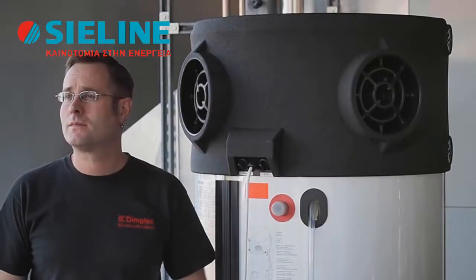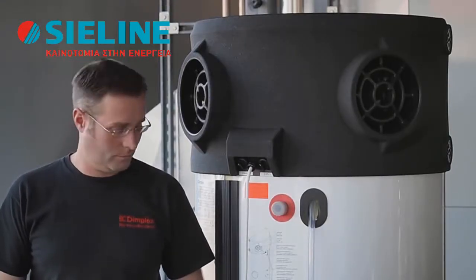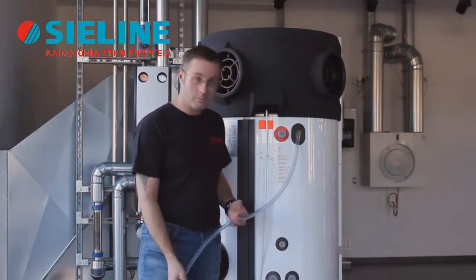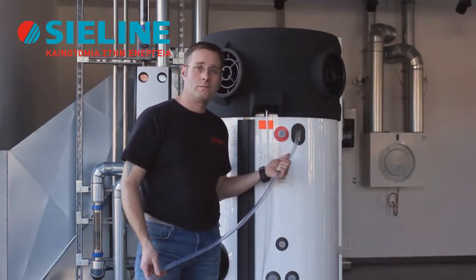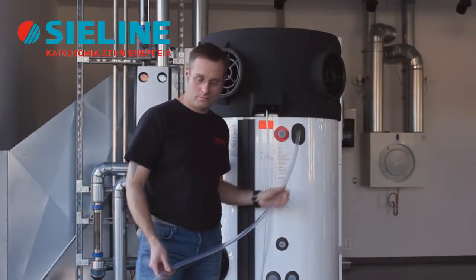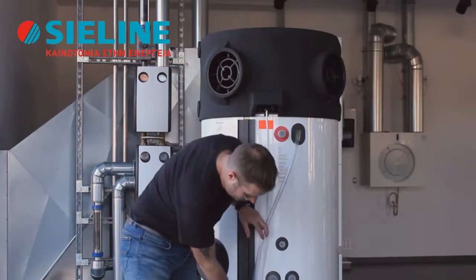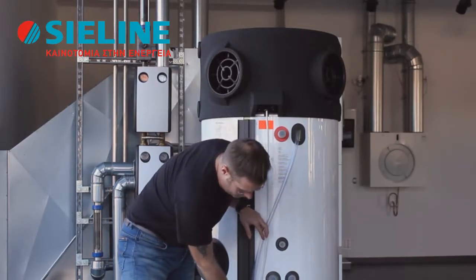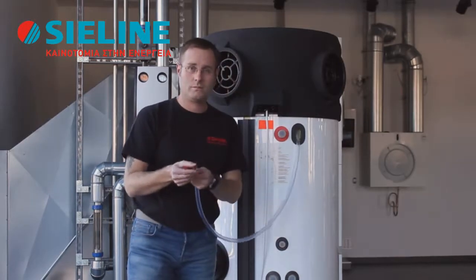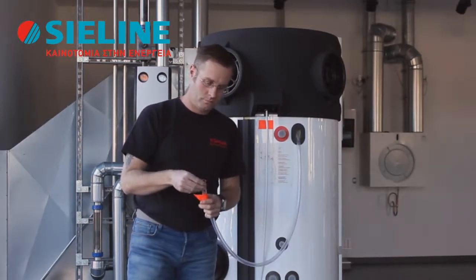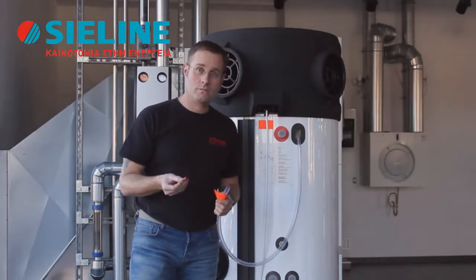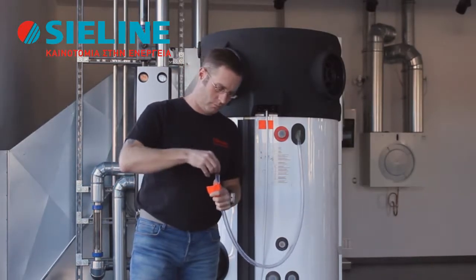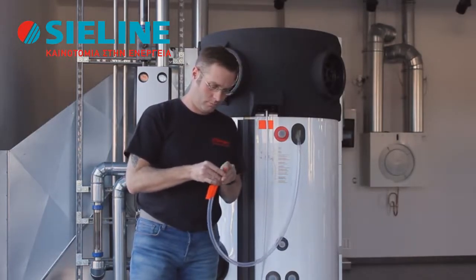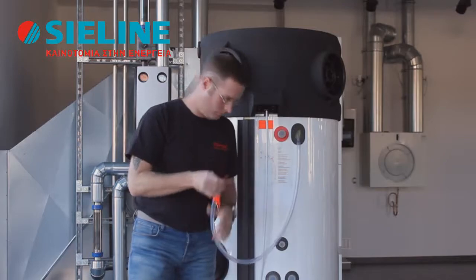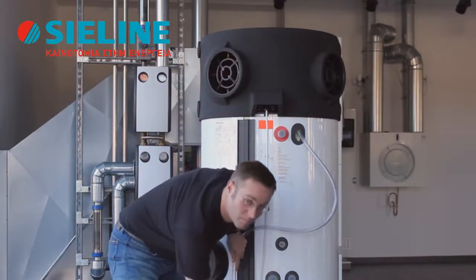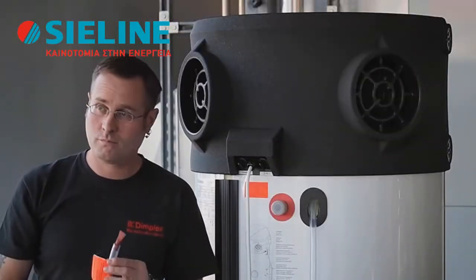free of corrosion. Very important is the connection of the condensate pipe, which is routed through the cladding of the rear of the device. It should be routed in such a way that the condensate produced during heat pump operation can flow away freely. There is a pressureless seal valve at the end of the condensate hose, which must be relocated accordingly if the condensate hose is shortened. The valve can be easily removed and reinserted. The condensate should be drained into a siphon. Please note, the sealing lip valve must be used to prevent damage from condensate.